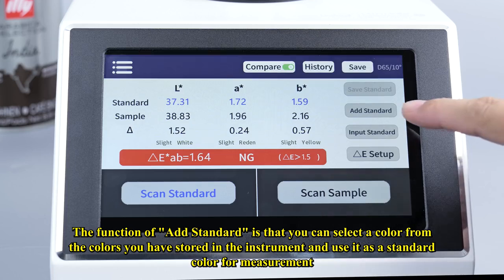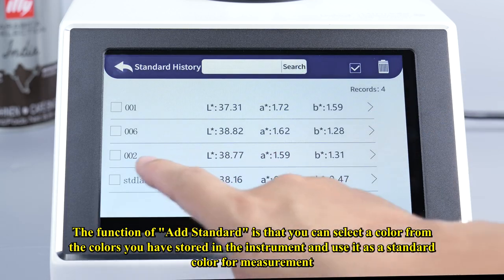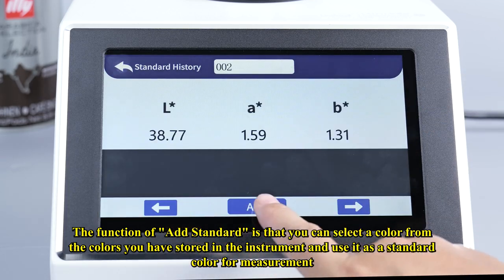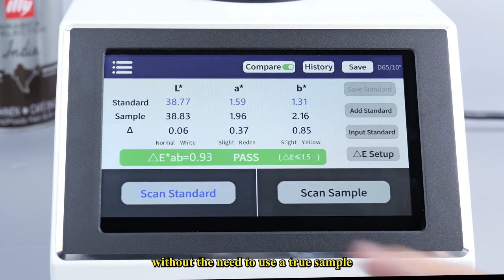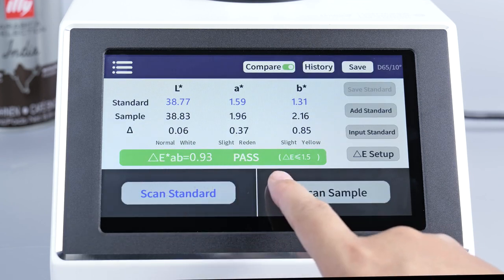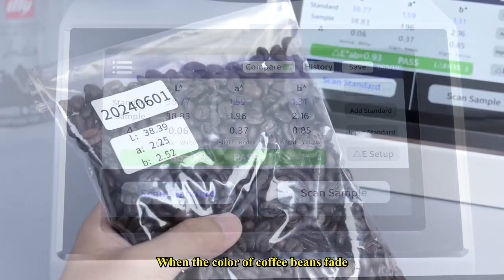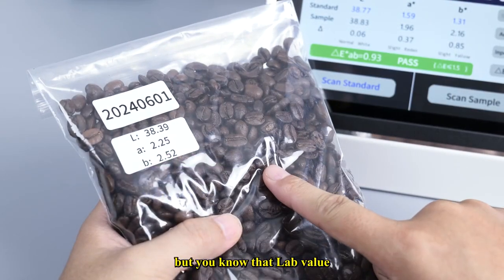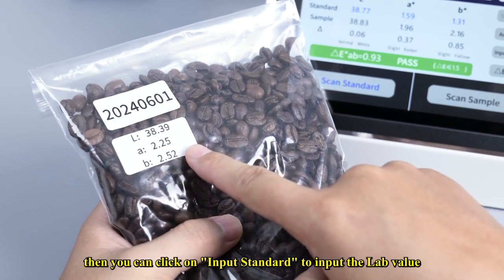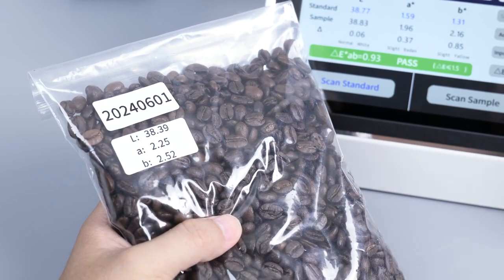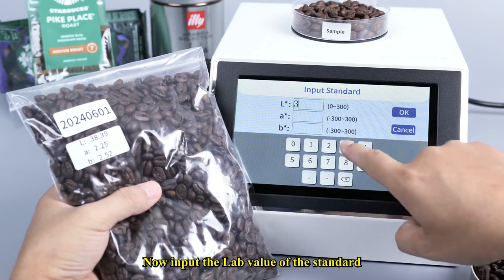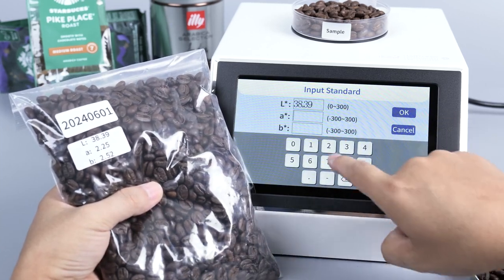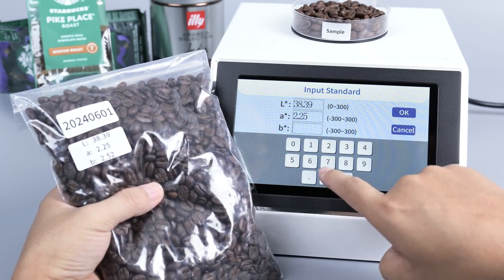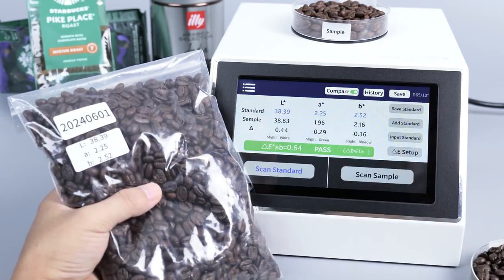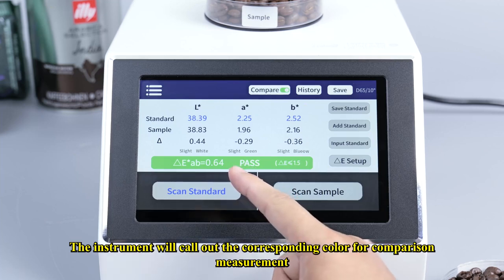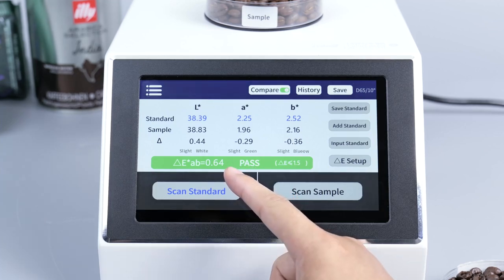The function of Add Standard is that you can select a color from the colors you have stored in the instrument and use it as a standard color for measurement, without the need to use a true sample. When the color of coffee beans fades, but you know the Lab value, then you can click on Input Standard to input the Lab value. Now input the Lab value of the standard. The instrument will call out the corresponding color for comparison measurement.